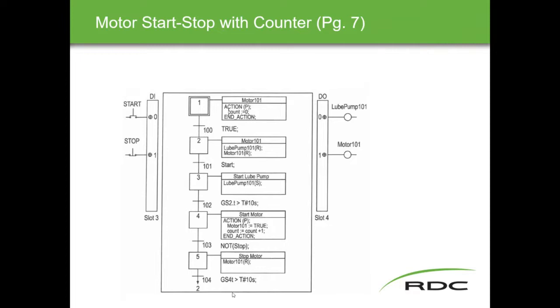GS2 timer at 10 seconds, GS4 timer here also at 10 seconds. So let's read through this and see what it says here. This program starts a lube pump 10 seconds before starting a motor and continues to run the lube pump for 10 seconds after stopping the motor. In addition, this program will count the number of times the motor is started. And here's how it works.